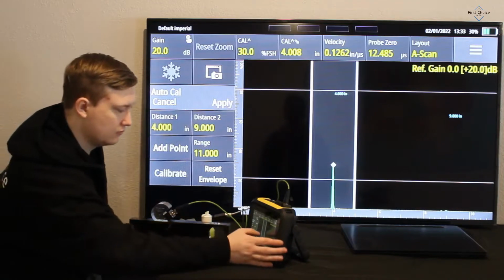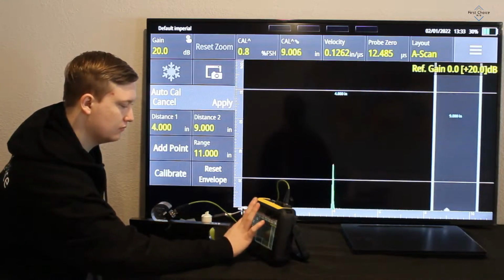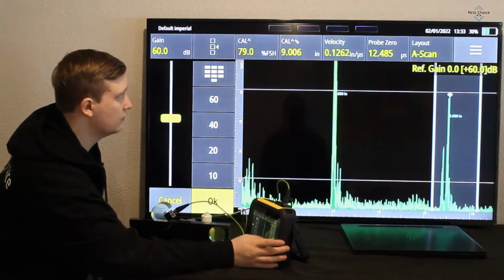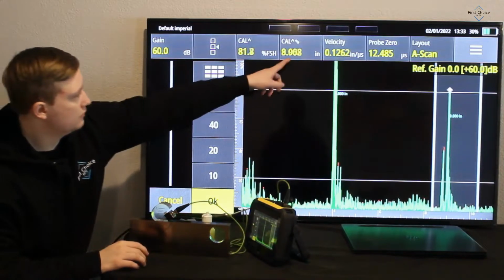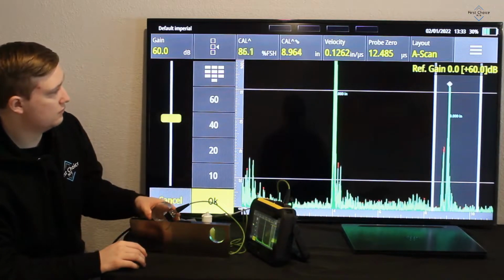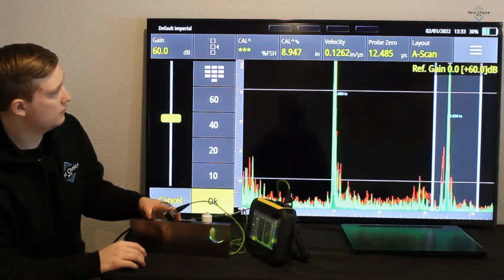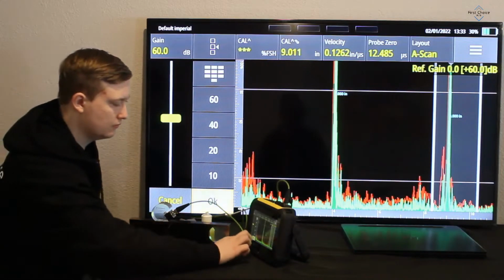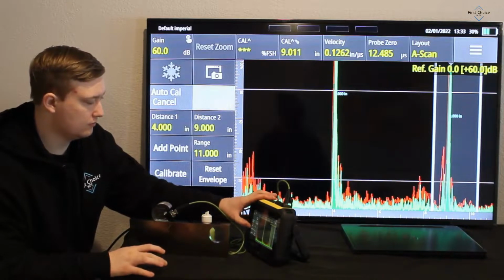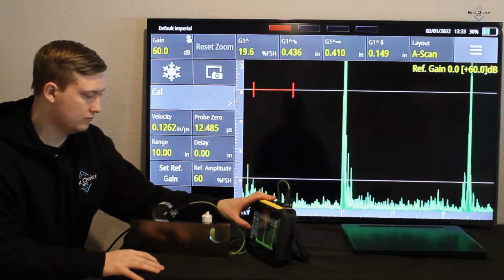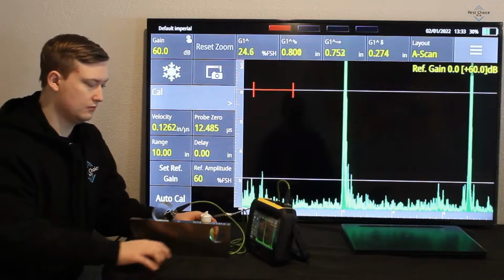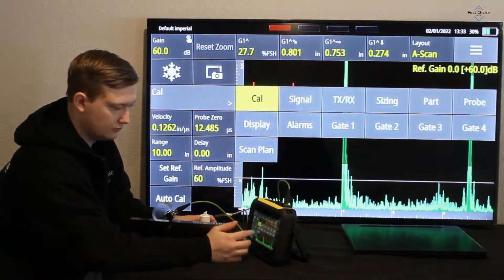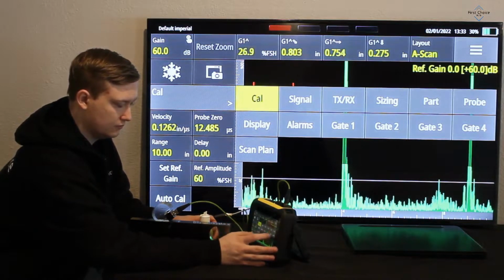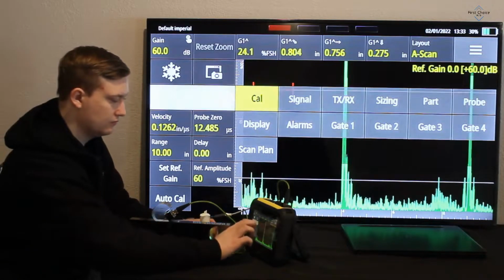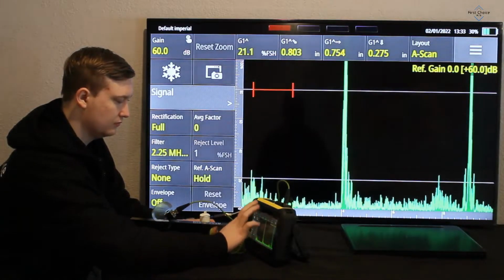So I went ahead, added that back point. So I added the 4 and 9 point. As you see, on the 4-inch mark, it's a 4.008, and on the 9 mark, it's 9.006, which is a fairly close calibration and pretty tight. And also, once you're at this point on the block, you want to go ahead and look where the transducer is facing.